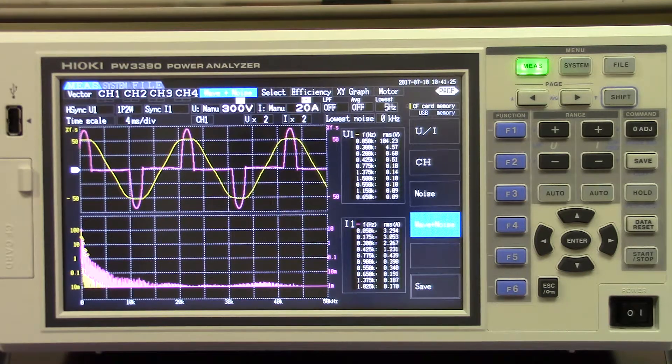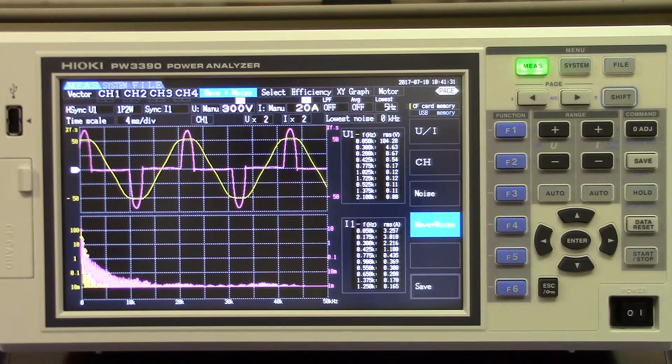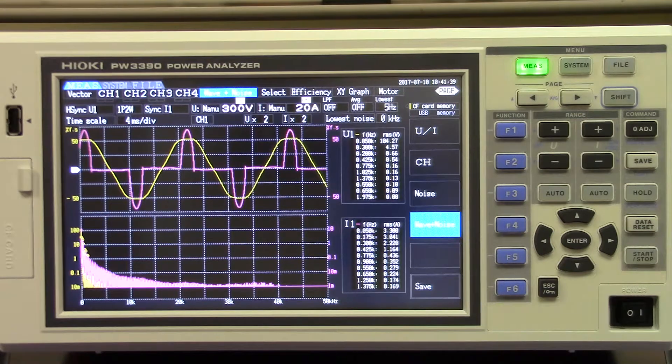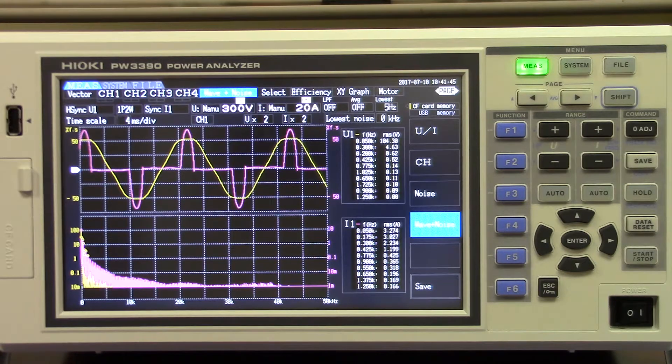Recorded data can be stored on a compact flash card then transferred to a USB jump drive right on the unit. The PW3390 also provides an Ethernet port and built-in HTTP server so the unit can be accessed and remotely controlled through a PC's web browser. Up to four 3390s can be daisy-chained and synced together to provide up to 16 channels of analysis.